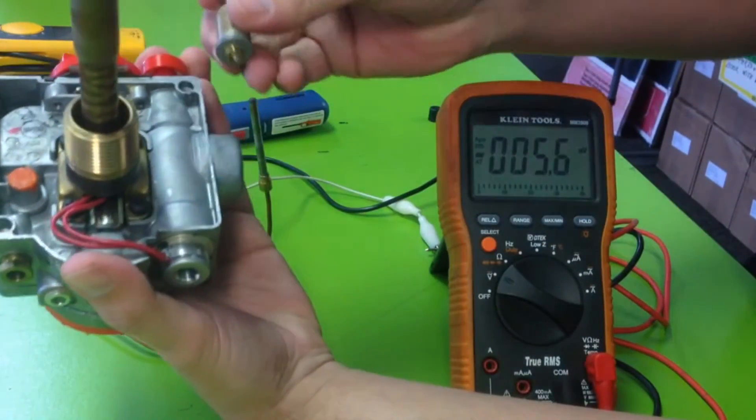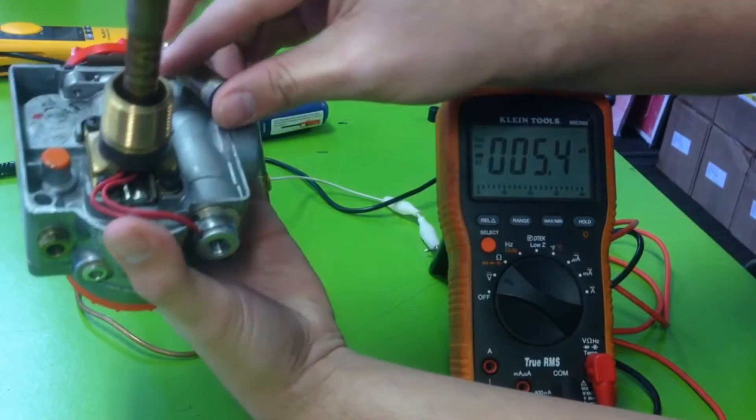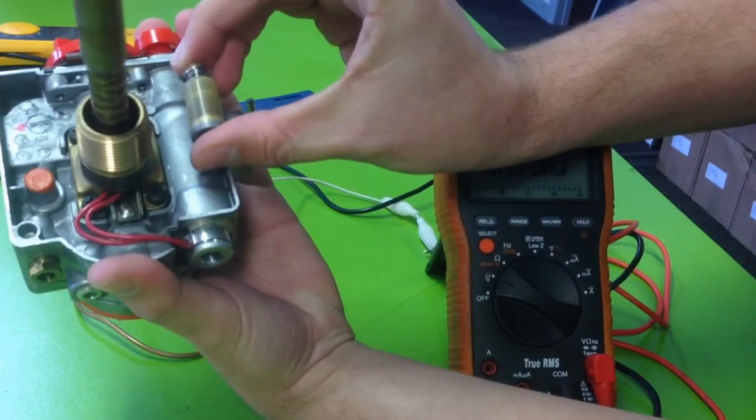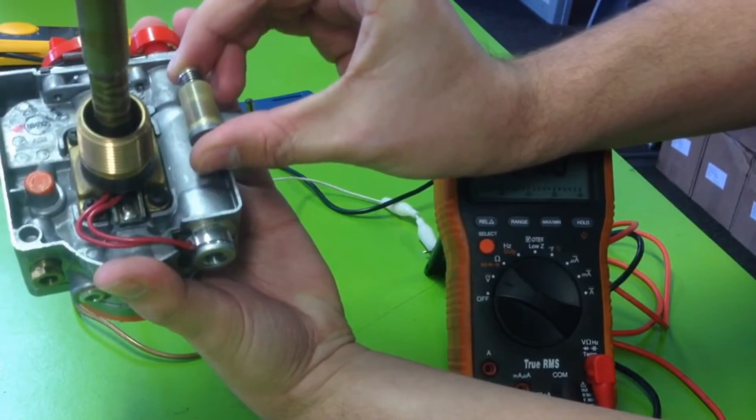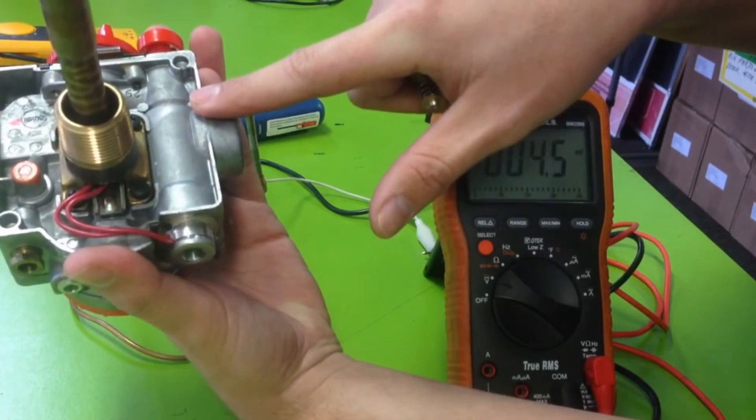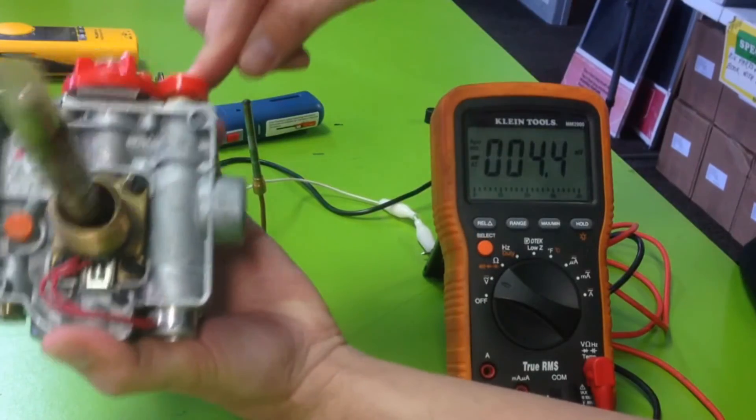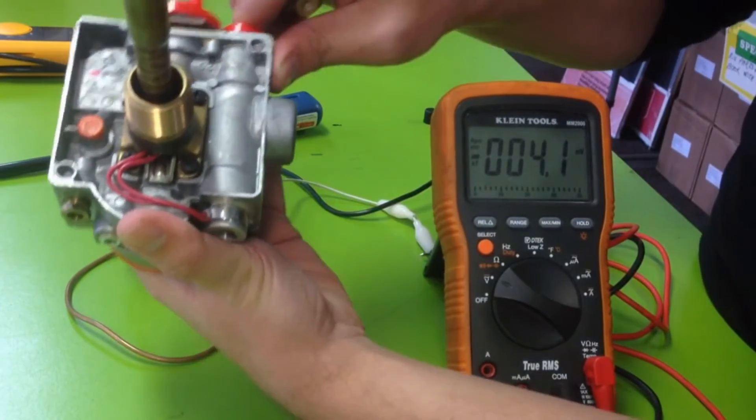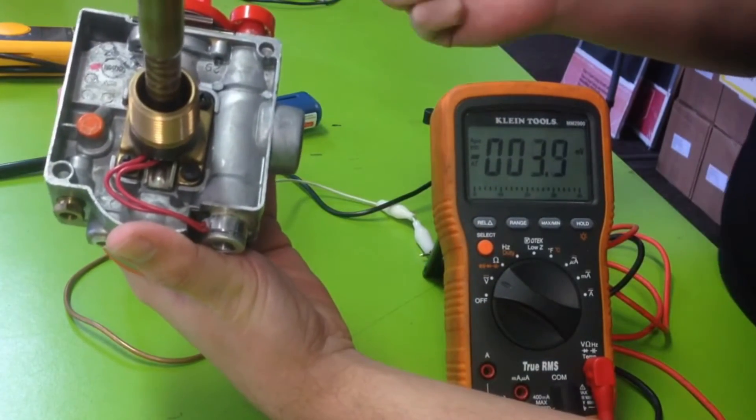So when I press that button, this internal piece goes down and makes contact and it stays depressed, which lets the gas flow through the inlet. Basically, if you press your button down on your control or your furnace, whatever you're working on, and it's not staying depressed when your pilot's lit, you probably have a bad thermocoupler or bad control.